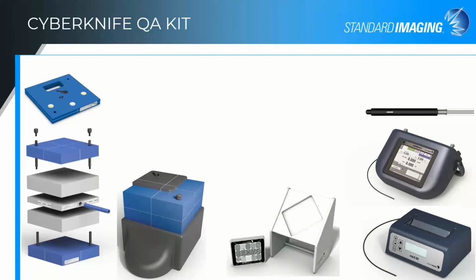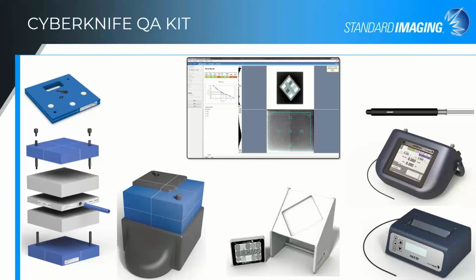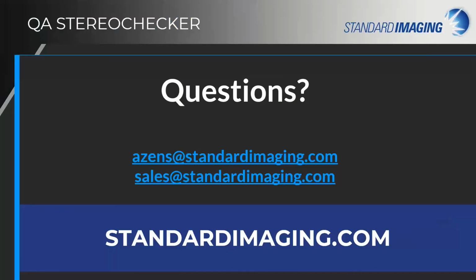Finally, our QC kV phantom and accompanying PIPS Pro software are excellent tools to perform QA on the kV imagers used in the CyberKnife system. And that brings me to the end of my presentation for today.